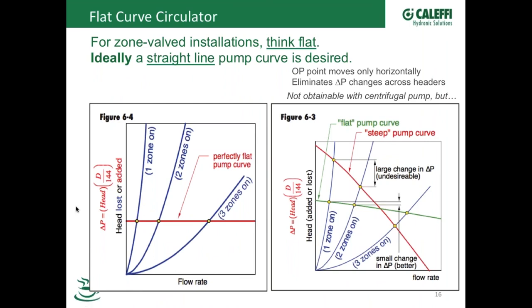All right, so now let's talk a little bit about circulators. Whatever system you have out there, if you're going to have zone valves somewhere in the system, you're still going to need a circulator pump. Something's going to make the flow go through the pipes through the building. So it's not a matter of if you can just use zone valves, you're still going to have a circulator.